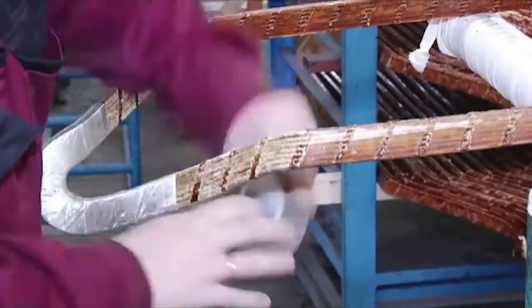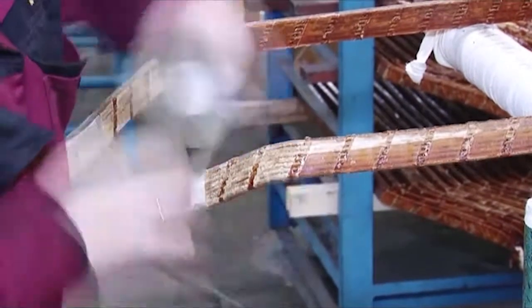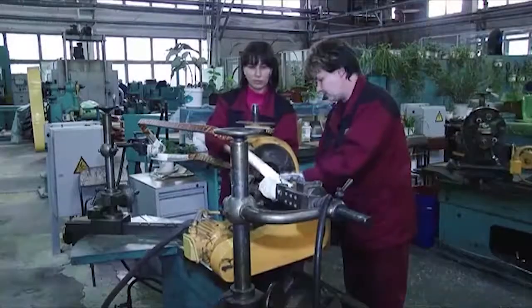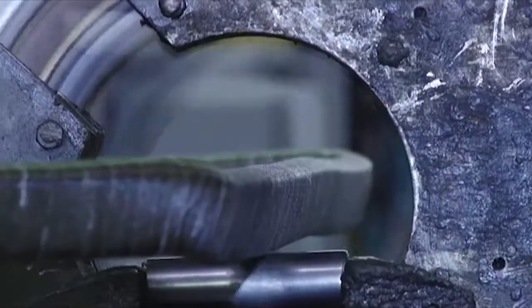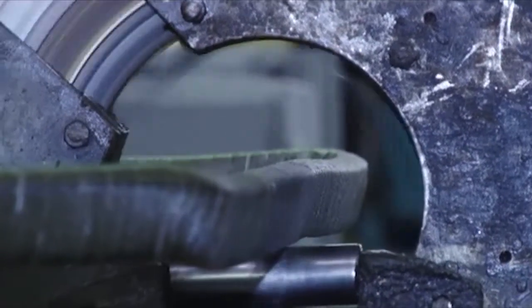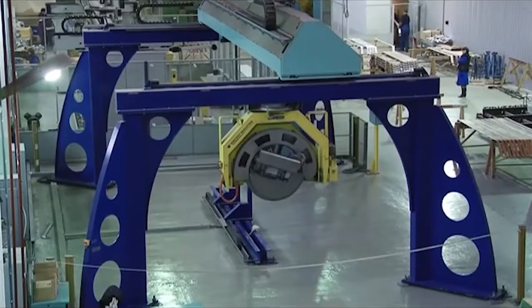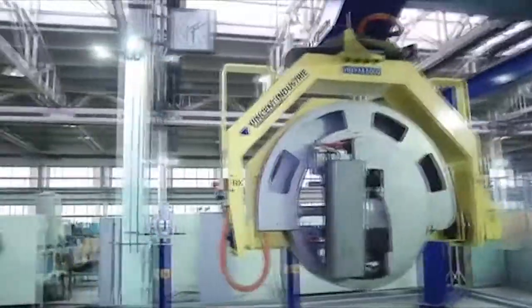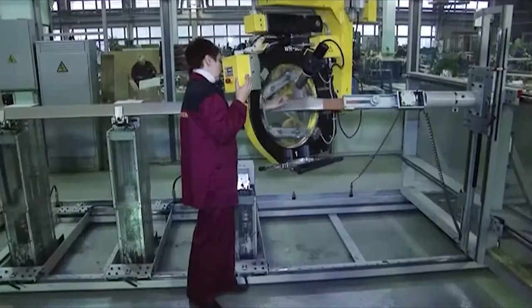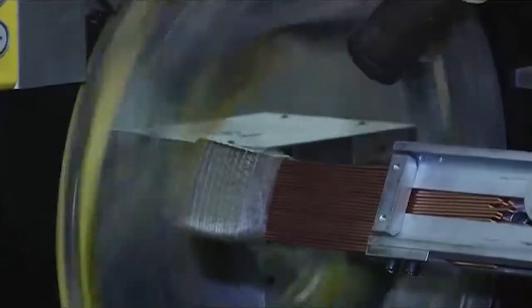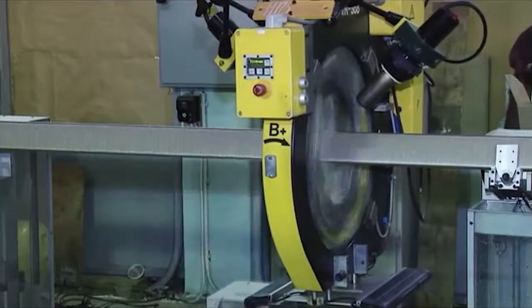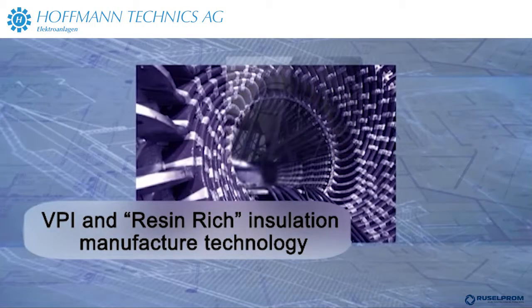Part of the stator coils and winding sections, up to approximately the middle, is insulated manually. The rest of the winding section and the slot section are insulated mechanically. Our enterprise also has a set of bar bending and insulation taping equipment, which is used for the manufacture of large hydro generators. The set consists of two machines. One is used for the bending of end winding sections, the other for the insulation taping all along the bar. The insulation tape is wound with a certain tensioning effort, which is adjusted automatically to the required value.